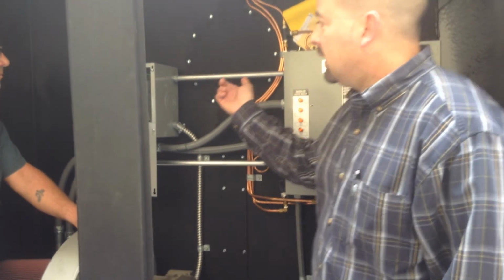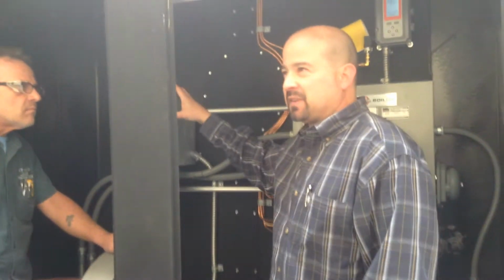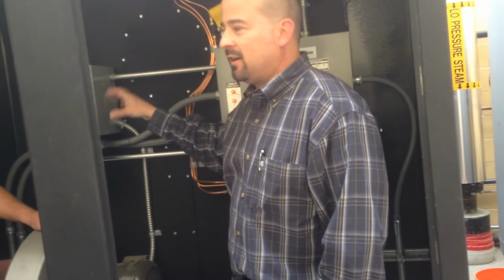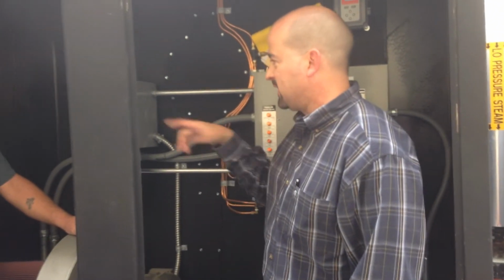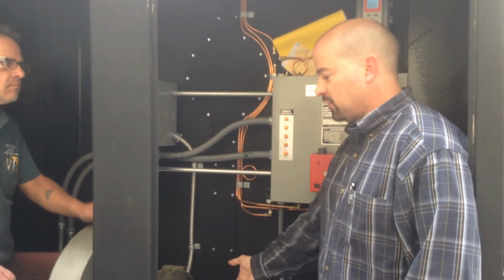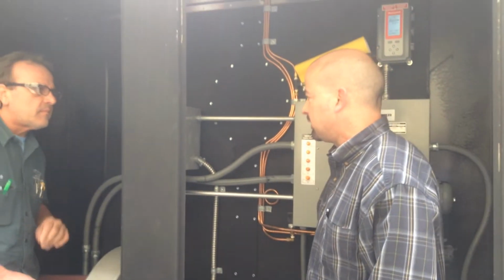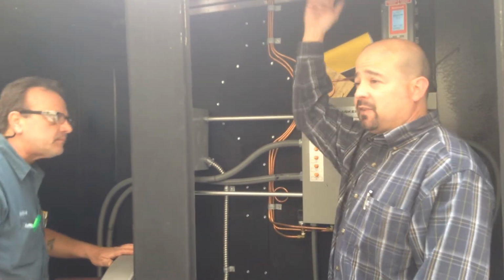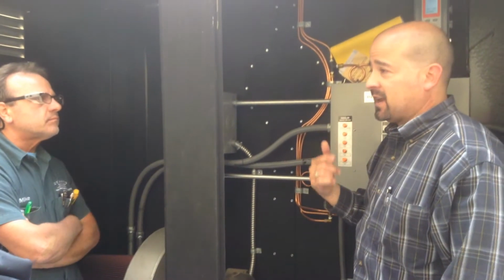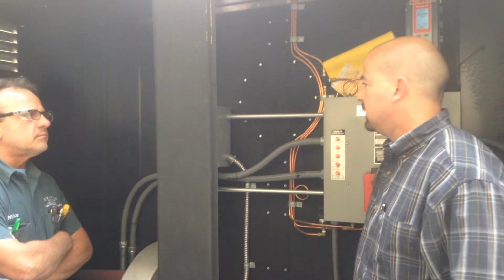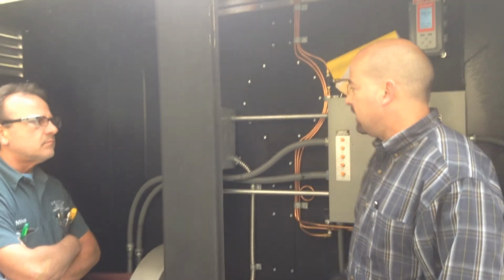You're in high fire. Don't make the mistake that 60 hertz is high fire. High fire is what we set, what we tell it to be, based on pressure readings of the manifold and what the factory wants. Every job is different. You might have 100 feet of stack on it. You might have 10 feet of stack. Everything affects the fire rate.